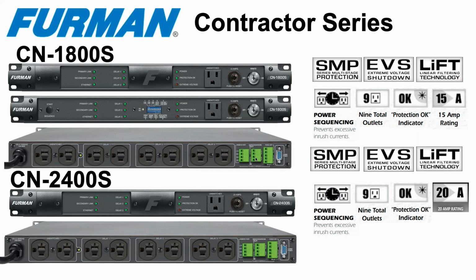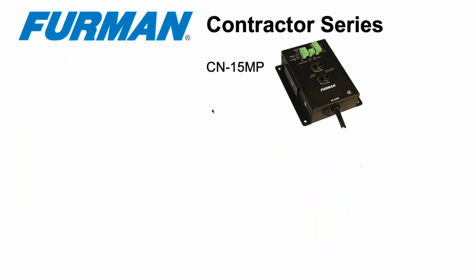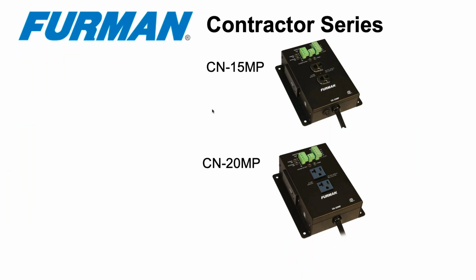They could be 1,000 feet apart on 24 gauge unshielded twisted pair, and it uses a current feedback loop for the information. You can literally go 1,000 feet apart with these, up to 50 units altogether. That first one in the chain will be your controller for everything. So even with that RS-232, you can control any of those 50 devices within the chain. And it could be a mix and match of CN1800Ss and 2400Ss, along with our CN15 MPs or 20 MPs as well, which are great modules to put in remote areas if you need to.